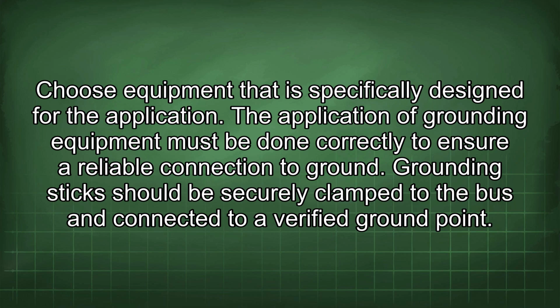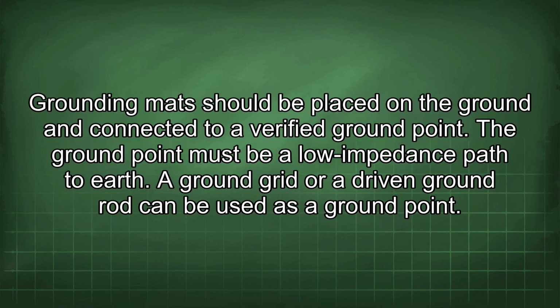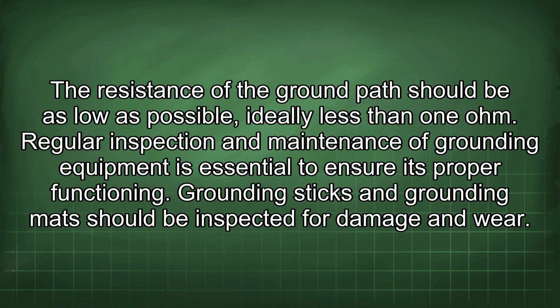Grounding sticks should be securely clamped to the bus and connected to a verified ground point. Grounding mats should be placed on the ground and connected to a verified ground point. The ground point must be a low impedance path to earth. A ground grid or a driven ground rod can be used as a ground point. The resistance of the ground path should be as low as possible, ideally less than 1 ohm.